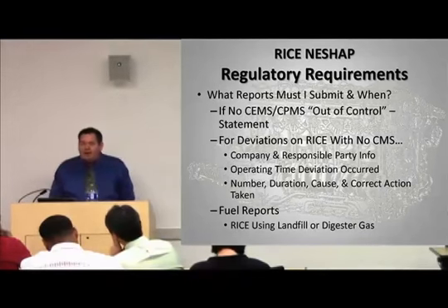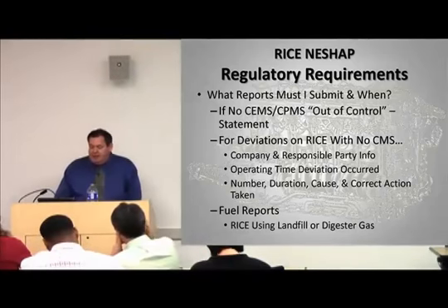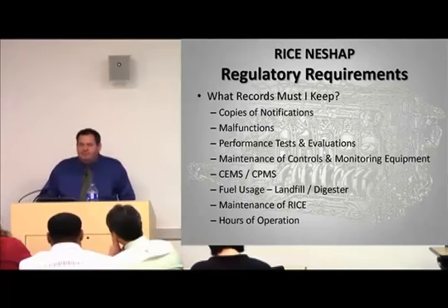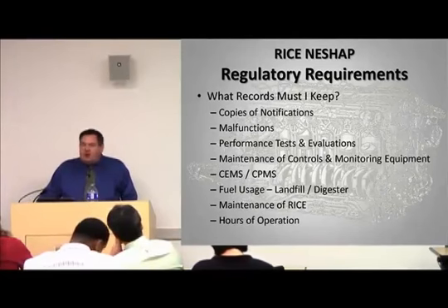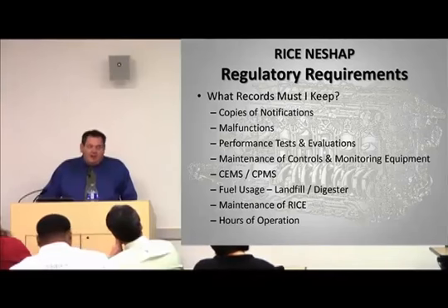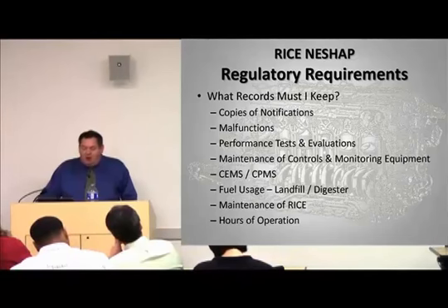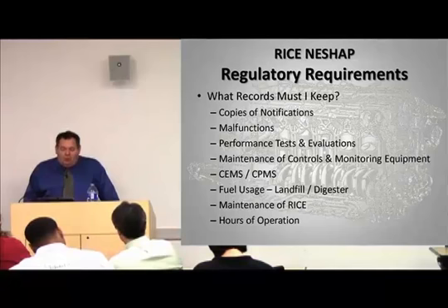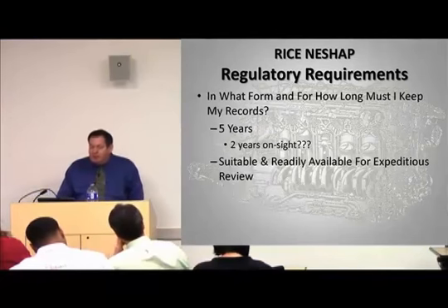And the fuel reports, this is back to the landfill digester gas: is 10% of the heat derived from landfill or digester gas. Records, what must you keep? Everything we've just described. All of your notifications, all documentation relative to malfunctions, performance tests and evaluations, maintenance of controls and monitoring equipment, CEMS and CPMS, fuel usage if you're using landfill digester gas, all your maintenance records for your operation of your RICE, and hours of operations for those engines that have operating limitations: emergency engines, limited use engines, engines used less than 24 hours per year.